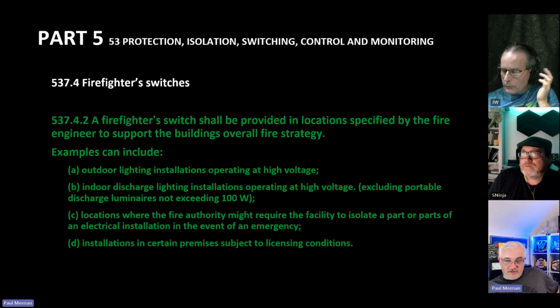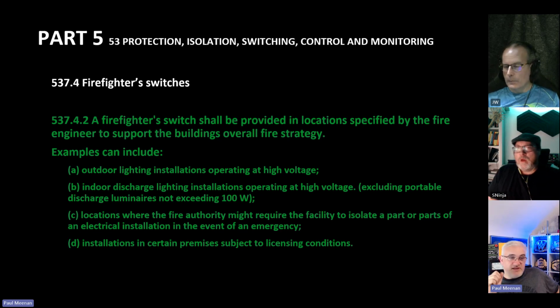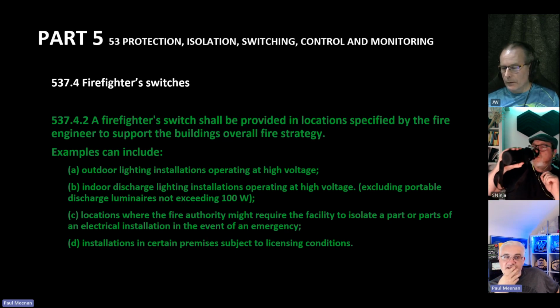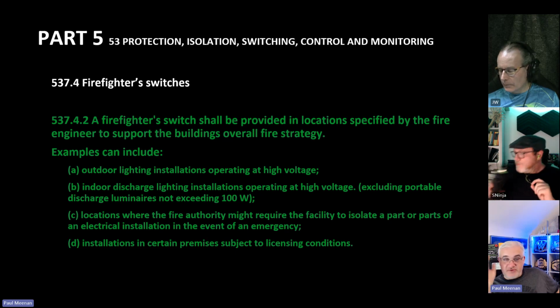Now, examples of firefighting switch can include outdoor lighting - we know some of the old stuff goes up to high voltages - indoor discharge lighting, locations where the fire authority might require the facility to isolate a part or parts of an installation in the event of emergency, and installations in certain premises subject to licensing conditions. So this is part of this new reg. Now, firefighter switches used to be just for the outdoor lighting, high voltage stuff, and that was it.